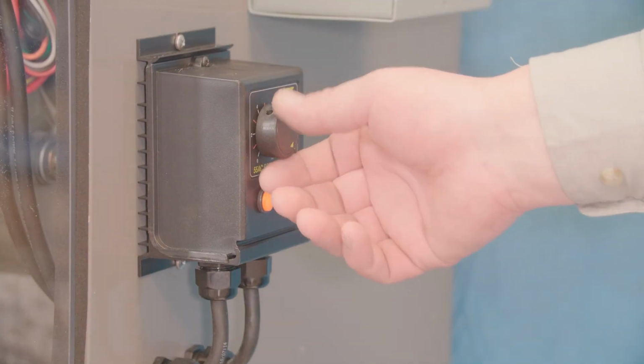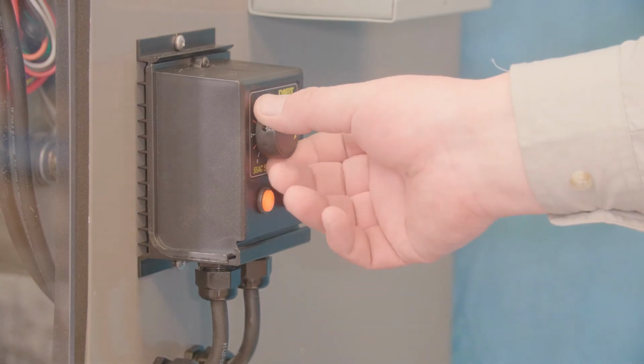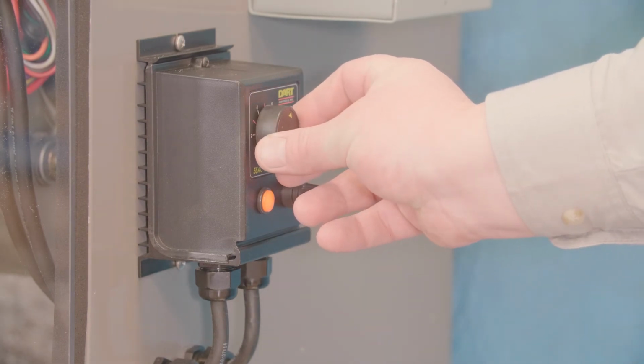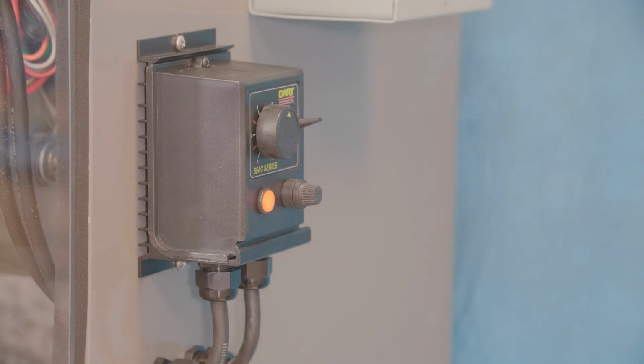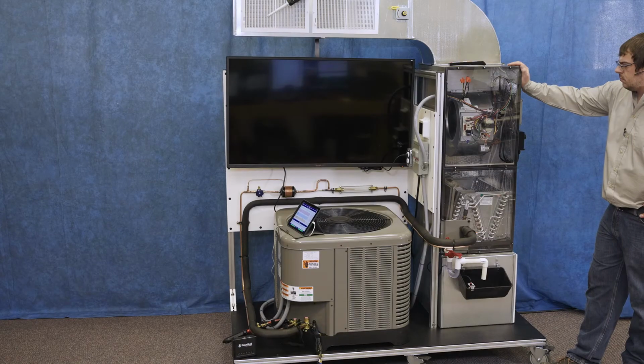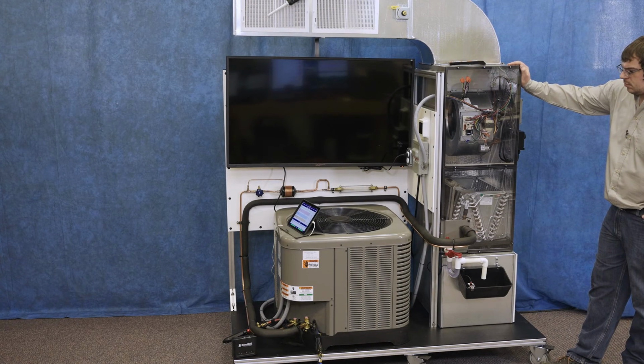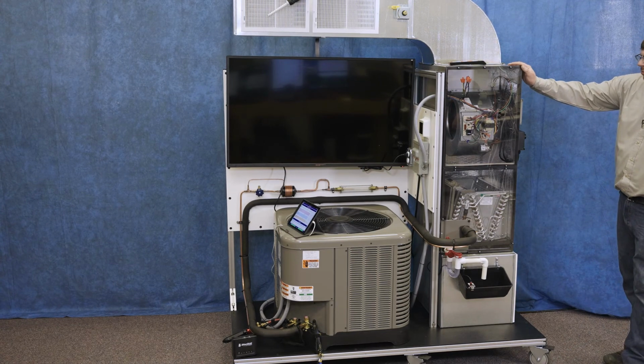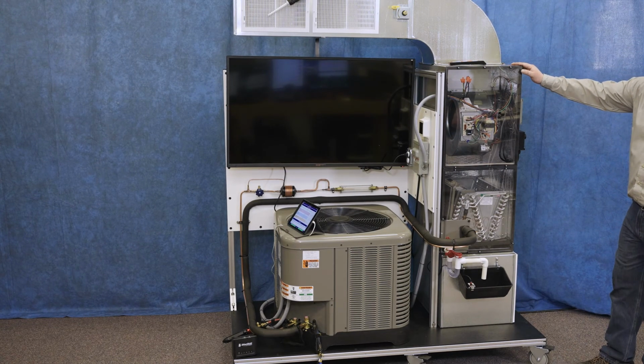So that's how we know that that is a PSC motor, a permanent split capacitance motor, that it's got that capacitor in there. We can clearly see it. All right, so Nick, what I want you to do is we'll have an amp meter on the motor itself to see how it is affected by airflow. One of the things that I like to teach students, and what's great about this 406C, is we can see how to measure the effects of airflow on the motor without having to take out a lot of extra instruments.